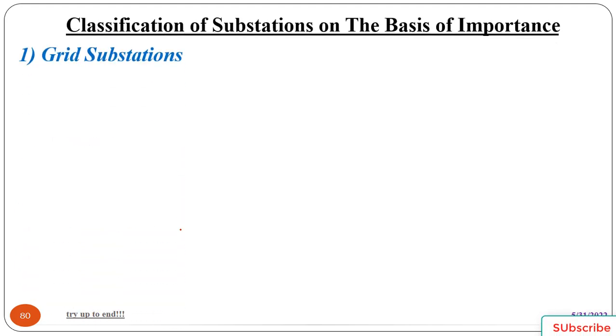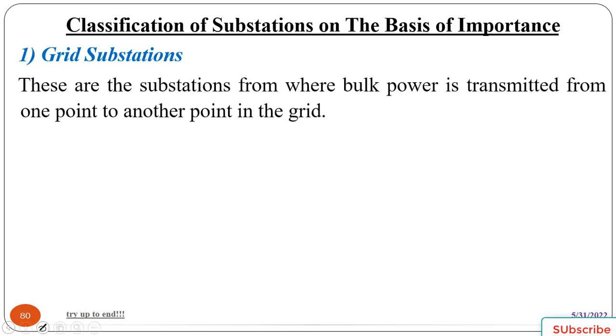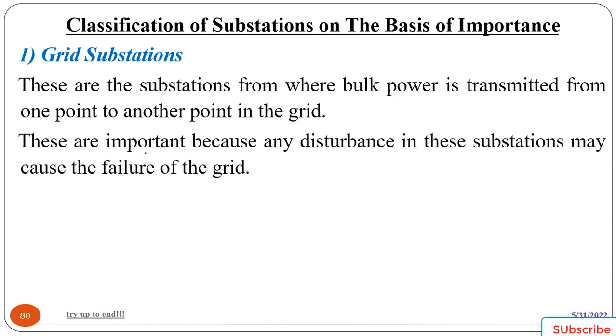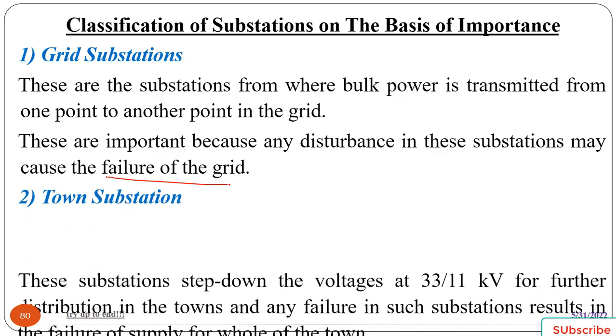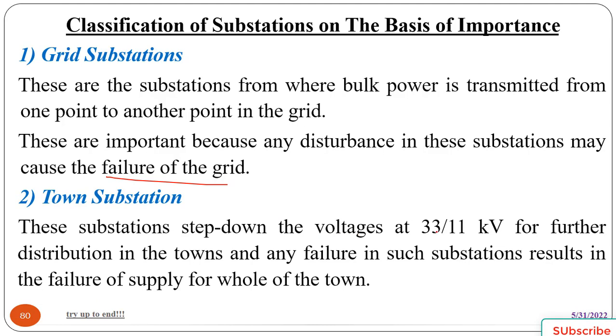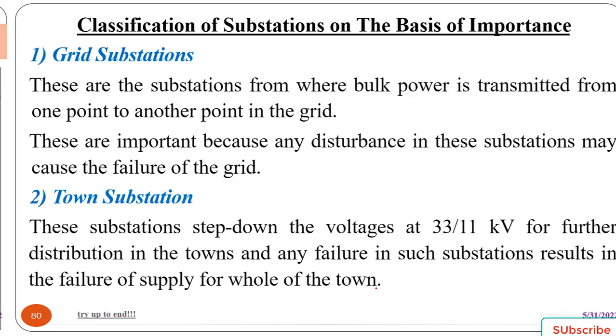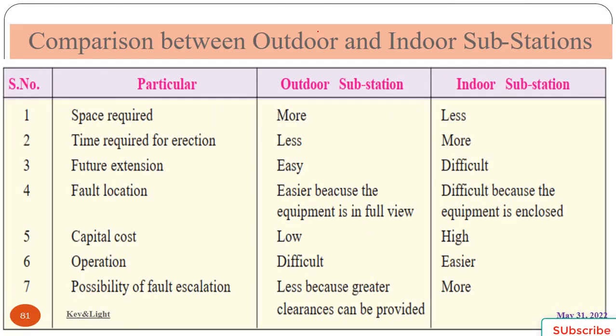So there is a classification of substations based on importance. Grid substations are substations from where bulk power is transmitted from one point to another point in the grid. These are important because any disturbance in such a substation may cause the failure of the grid. The other is the step-down substation, which steps down 33 to 11 kV for further distribution in the towns, and any failure in such a substation results in the failure of supply to the whole town.